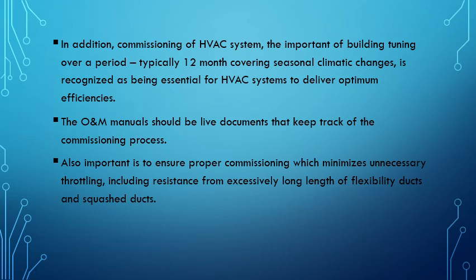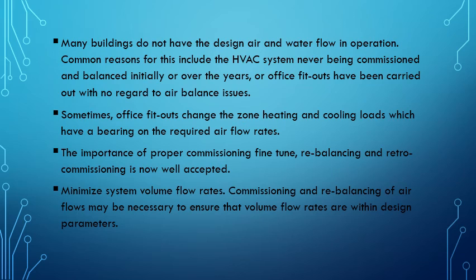The operation and maintenance manual should be a live document that keeps track of the commissioning process. It is also important to make sure of proper commissioning, which minimizes unnecessary throttling, usually including the resistance from excessively long lengths of flexible duct and squashed duct. So many buildings don't have the design water and airflow operation. A common reason for this is that the HVAC systems are not commissioned and balanced initially or over the years. So that's why, if you are not doing any commissioning process, the document that shows the specification of the system, the entire HVAC system, is not there. So that's why there will be problems in the future.